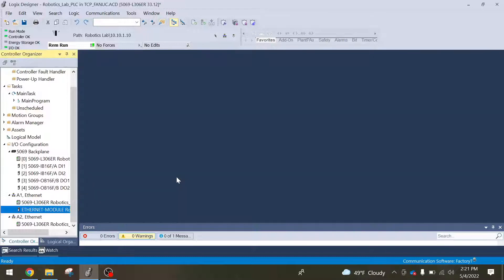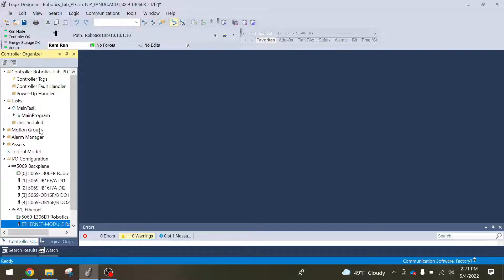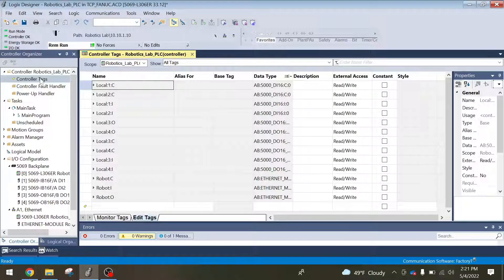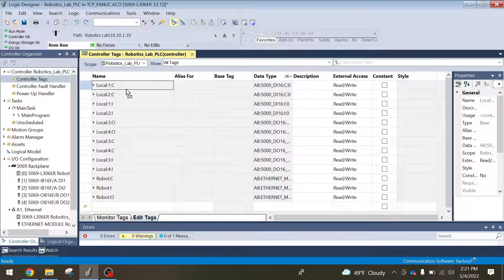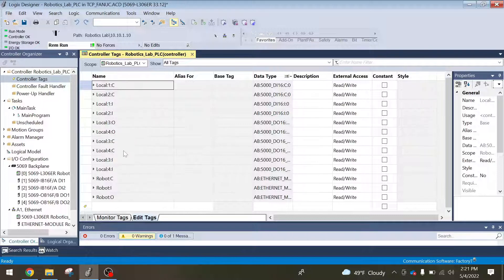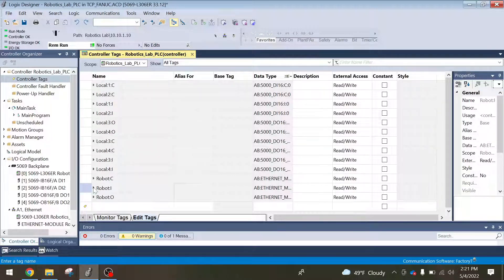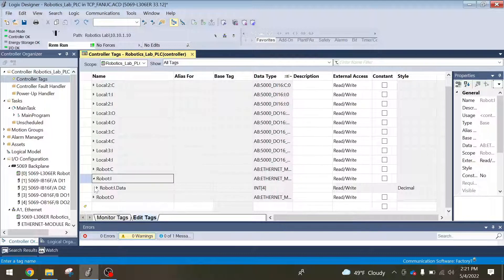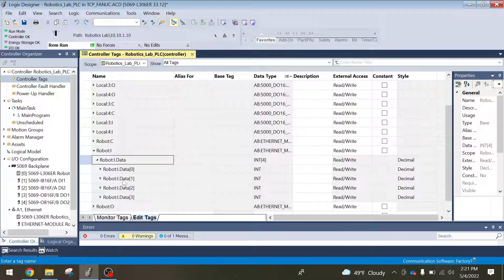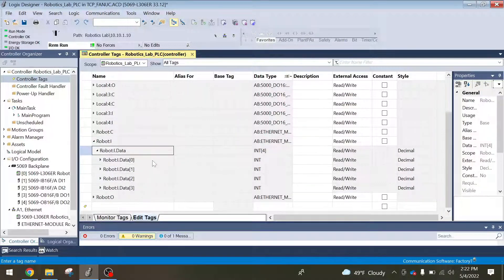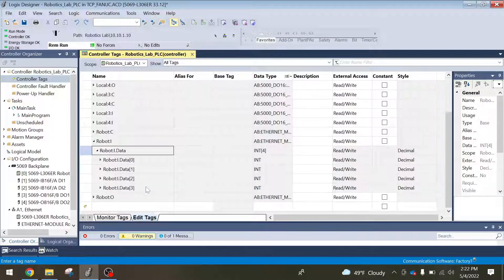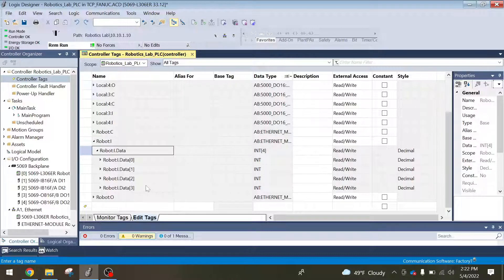Now I want to show you how the inputs and outputs come into Studio 5000 from the module. You can scroll up, you can go to controller tags, double click, and this will show you all of the input output slots that I have on the PLC itself. Then on the bottom here, it'll come in that generic Ethernet module. I'll have my robot inputs, my robot outputs. If I just go into my robot inputs, go down to the data. Now you'll see four 16-bit words that are transmitted. This corresponds directly to what we set up in the Ethernet module and the robot side. If we were to set up eight 16-bit words, there would be eight of these, so zero through seven.